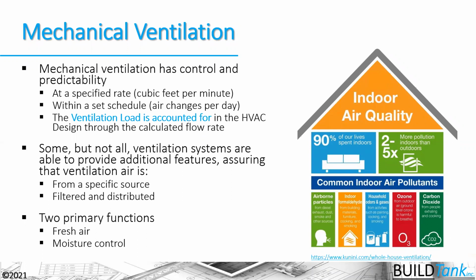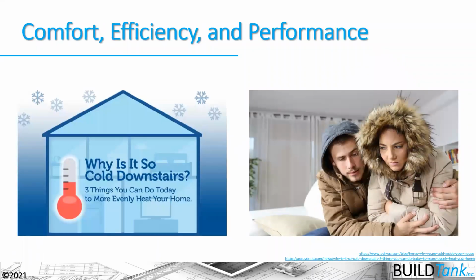Now, there are some ventilation systems that are able to provide these additional functions, and those are generally balanced ventilation systems that can tell you where the air is going in and out of the house and the specific source and location where that's happening. And you might also be able to add filtration to that air and distribute that air by better means around the house. But the primary function overall of mechanical ventilation, regardless of the type of ventilation that you're using, is to provide fresh air for the occupants and to provide background moisture control in our houses. And that ultimately helps us achieve better comfort, efficiency, and performance in our homes if we have good ventilation systems and we've built our houses as tight as possible to limit the air leakage load, or the infiltration load, that's happening in our houses.